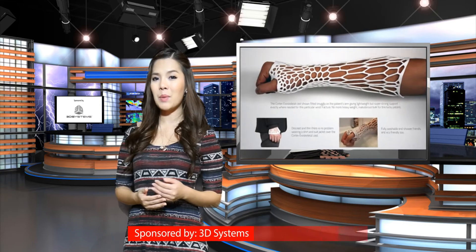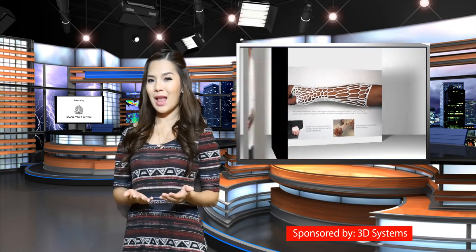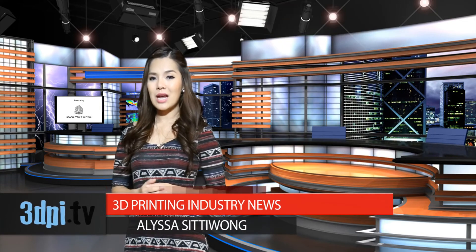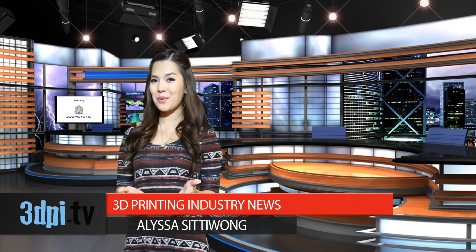In the osteoid case, the ventilation openings are also used to implement a low-intensity pulse-ultrasound bone-stimulation system which needs to be applied directly to the skin and could thus not be used in a traditional medical cast. Used in a daily 20-minute session, the system could reduce healing times by 38% and increase the heal rate up to 80% in non-union fractures.